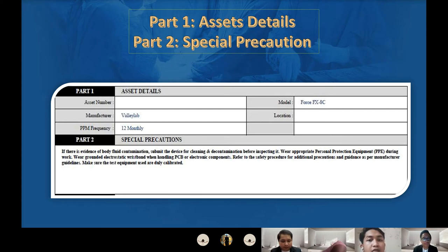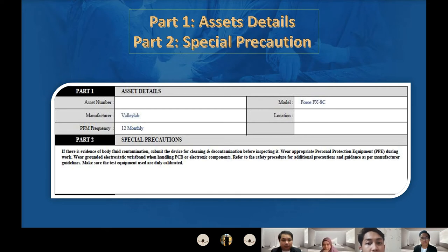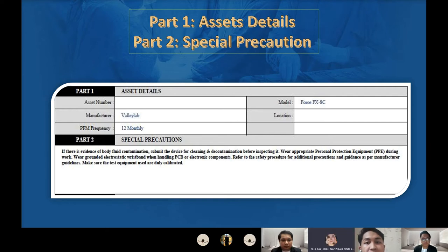Moving on to part two, special precautions. First, if there is evidence of body fluid contamination, submit the device for cleaning and decontamination before inspecting it. Wear appropriate personal protection equipment (PPE) during PPM work. Wear a grounded electrostatic wristband when handling PCBs or electronic components — this ensures any leaking currents will be grounded and ensures safety. Refer to the safety procedure for additional precautions and guidance as per manufacturer guidelines. And lastly, make sure the test equipment used are duly calibrated.